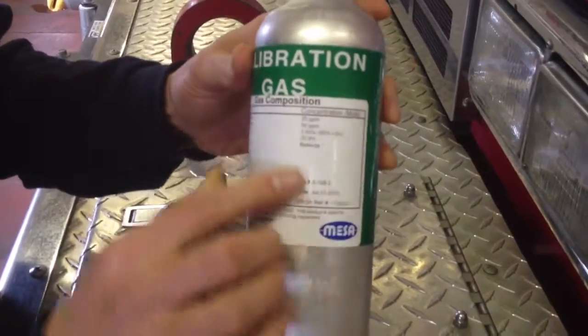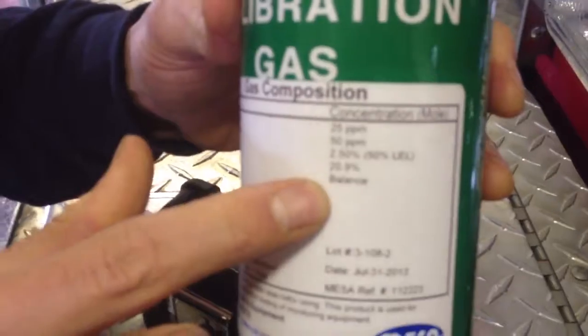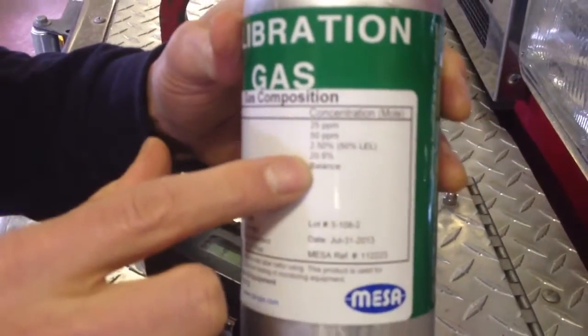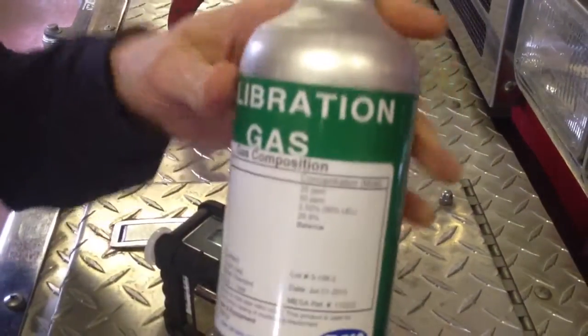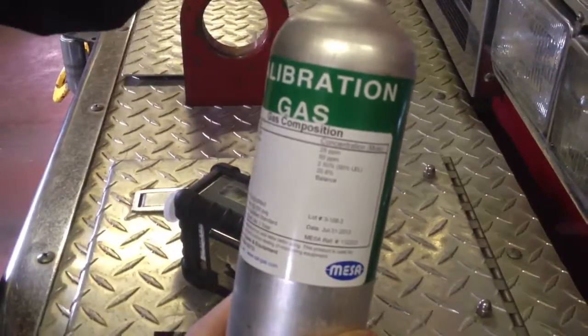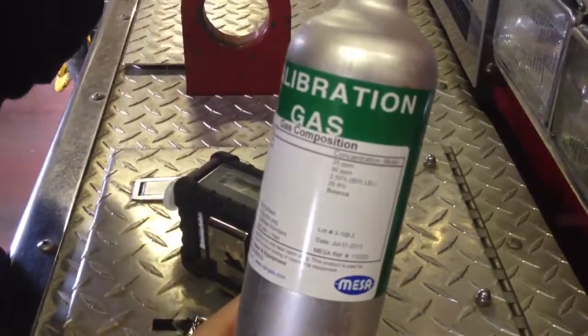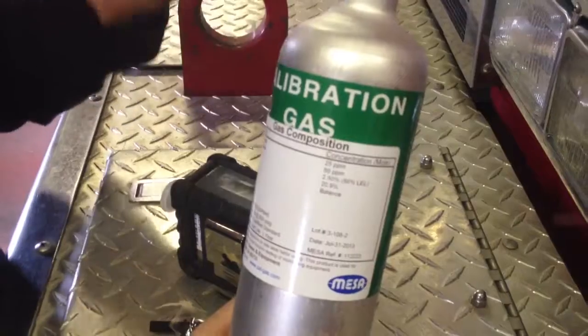So what we're going to do is apply the gas to the monitor while it's running, and we want to make sure these values come up. It doesn't have to hit all the way, it just has to be about 90%. We're just making sure we're getting a reading and that the sensor is actually functioning.